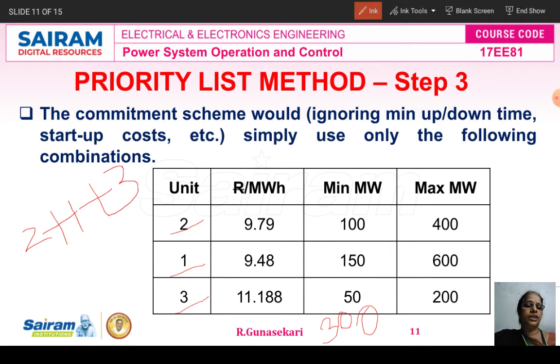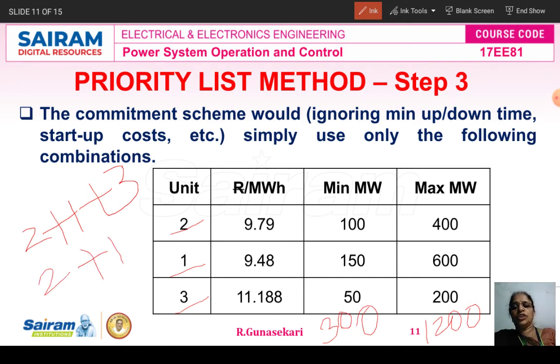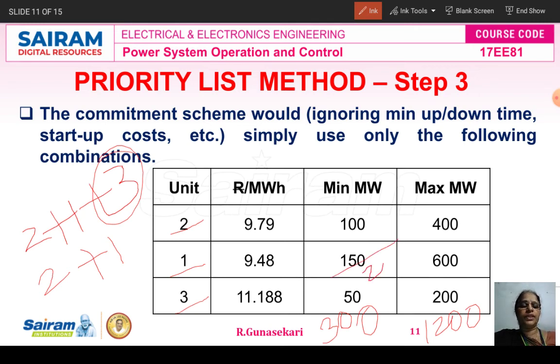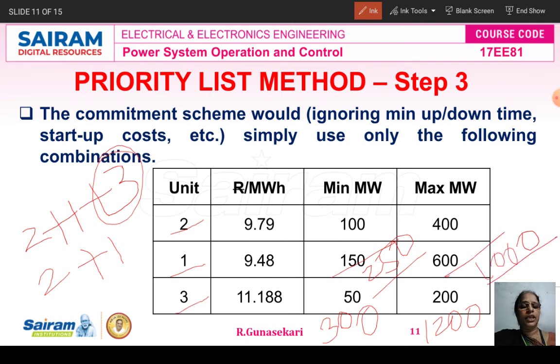The second combination is 2+1 — we remove unit 3 since it has the last priority. Only units 2 and 1 are synchronized. The minimum generation is 100+150 = 250 MW, and the maximum generation is 1000 MW. So the minimum dropped from 300 to 250 and the maximum from 1200 to 1000.